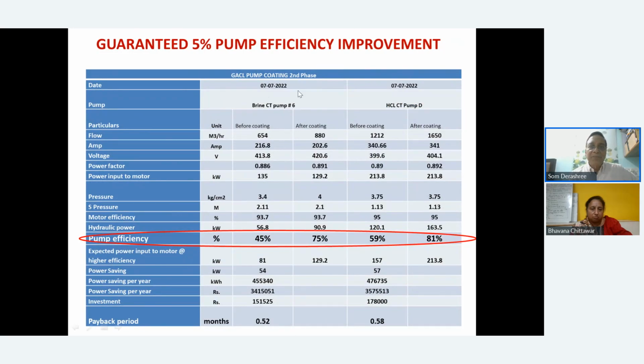You will see here is a cooling tower pump, 654 meter cube per hour, and it was taking 135 kilowatt. 45% was the pump efficiency. So we established a baseline first, which is jointly established, and after coating, again, you see the flow has increased tremendously. Of course, the pressure also has slightly fallen, but yes, almost the same. But the efficiency of the pump has improved to 75%, and thereby you're saving a lot of energy.